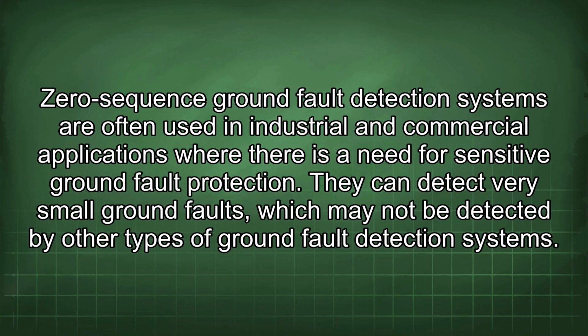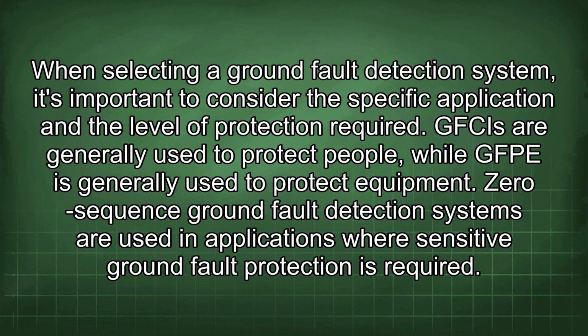Zero-sequence ground fault detection systems are often used in industrial and commercial applications where there is a need for sensitive ground fault protection. They can detect very small ground faults, which may not be detected by other types of ground fault detection systems. When selecting a ground fault detection system, it's important to consider the specific application and the level of protection required. GFCIs are generally used to protect people, while GFP is generally used to protect equipment. Zero-sequence ground fault detection systems are used in applications where sensitive ground fault protection is required.